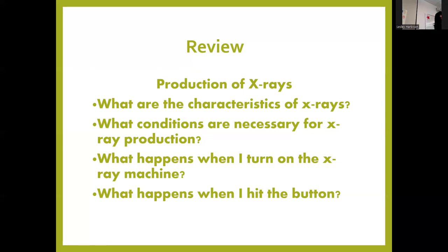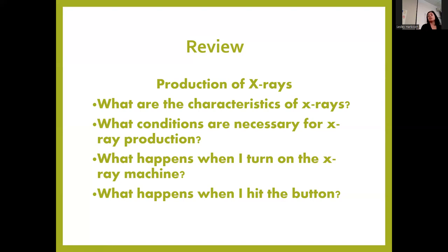What conditions are necessary for X-ray production? We need focusing, the electron source, the high voltage, and then the abrupt stoppage — something to stop them. When you turn the X-ray machine on, the first thing that happens is thermionic emission: the electron cloud starts forming around the tungsten filament. Then when you actually hit the exposure button, you get that high voltage and you're accelerating the electrons across.